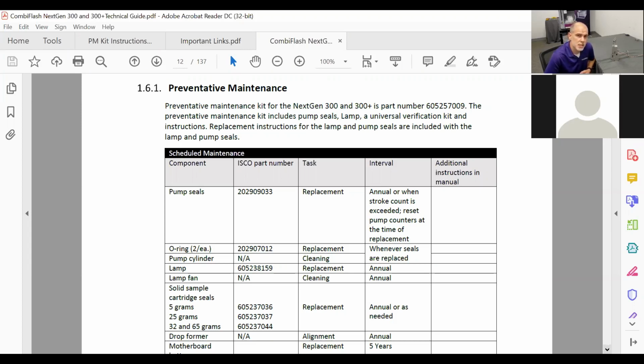The reason for that is because the kind of lamp that we use will overheat and destroy itself unless there's some kind of cooling done. As a kind of redundancy on that, we have a thermal breaker that's attached to that lamp, and I'll show that to you later when we're doing the PM. But if the lamp gets too hot, that thermal breaker opens and the lamp will not conduct. You'll get an error on your screen saying lamp failure, something like that. More than likely lamp failure. And one of the things you need to check is that thermal sensor. And I'll show you how to do that in just a little bit.